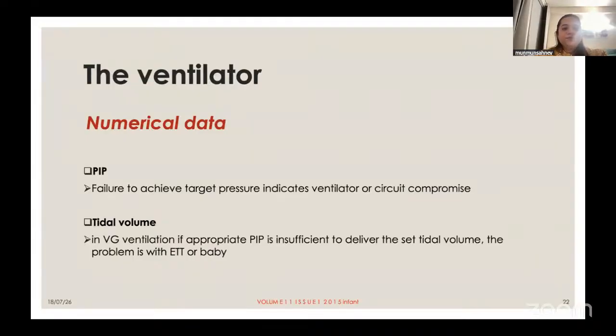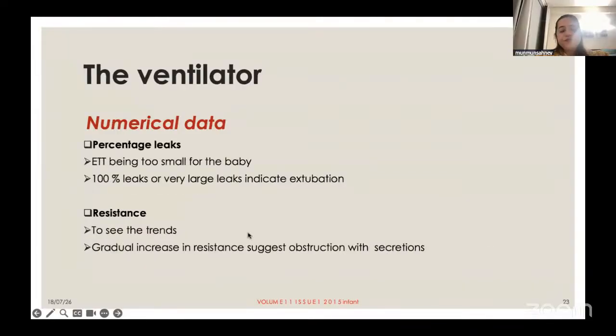The ventilator also has a lot of numerical data, which I had already discussed in the previous two cases, which we discussed in the starting. So the PIP, the set PIP is very important, and we should always look at what is being delivered to the baby. Similarly, the tidal volume, and we have already discussed that it's very important to set the baby on volume guarantee modes and to set an appropriate PIP max. The percentage leak again gives us an idea that something may be wrong with the ET tube or the circuit, and then resistance.